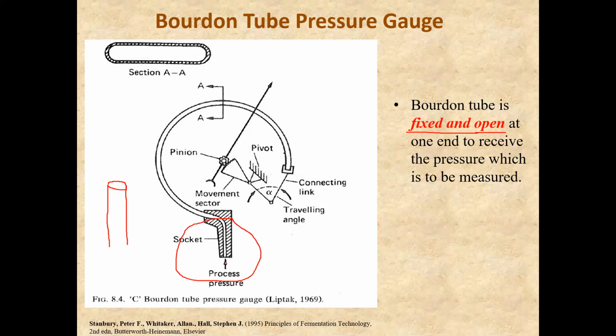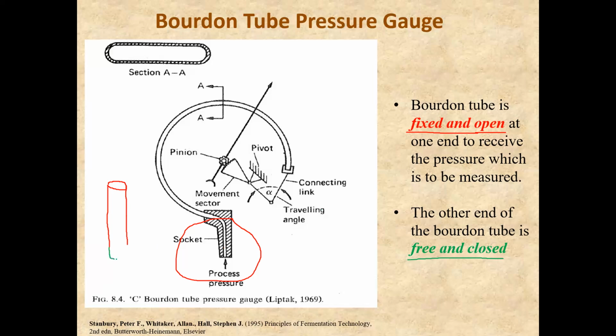This end is open so that it can take the liquid or whatever gas for which you want to measure or monitor the pressure. So it's open, but at the same time it is fixed. This end cannot move. And this is the end which will receive the pressure which is to be measured. The other end of the Bourdon tube is free and closed.